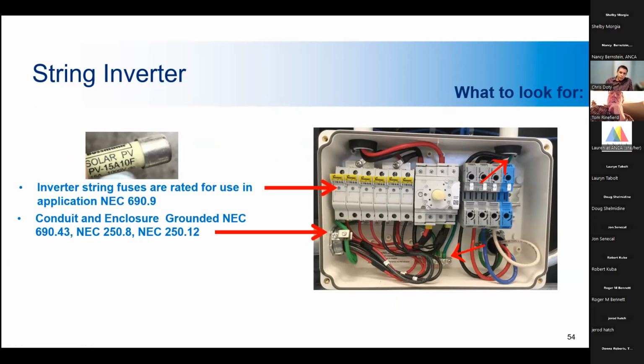In the string inverters, going along with this, take a look at the conduit bonding. That's crucial to a safe installation. You can see this is a plastic enclosure. So it's metal conduit, so you have to make sure that the metal conduit is bonded on each side and is bonded to the ground lug in the enclosure.